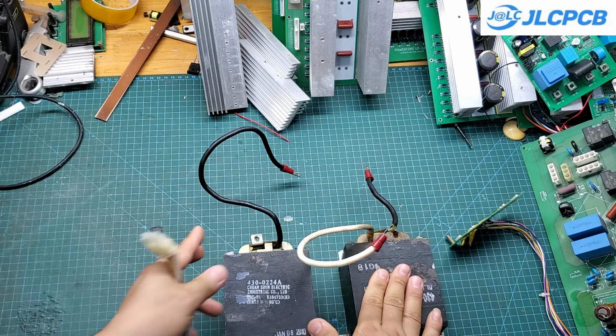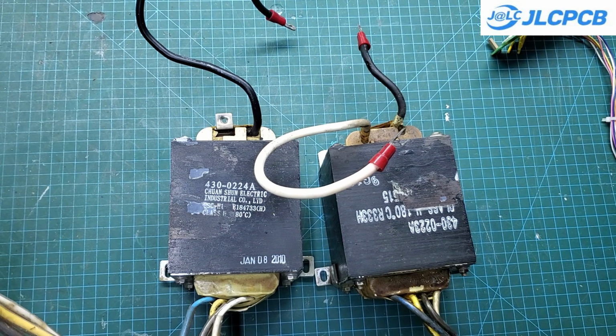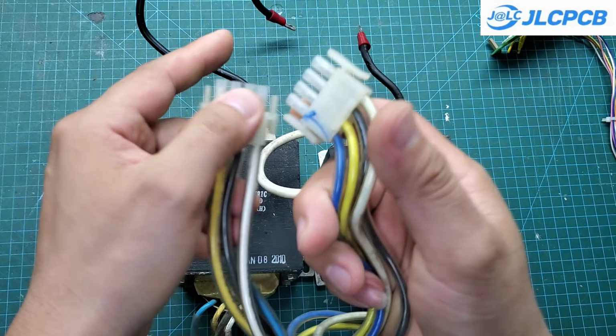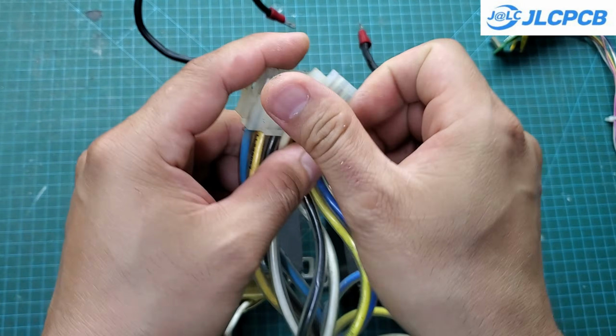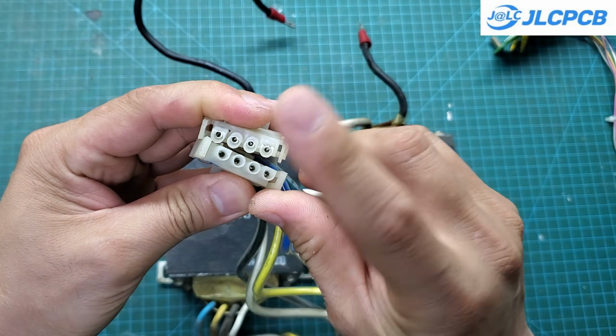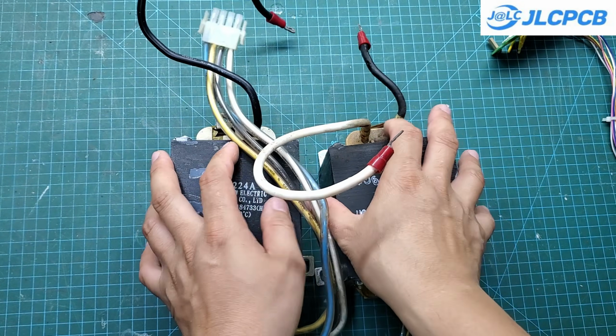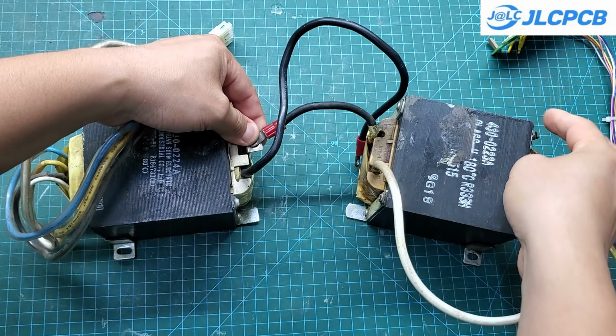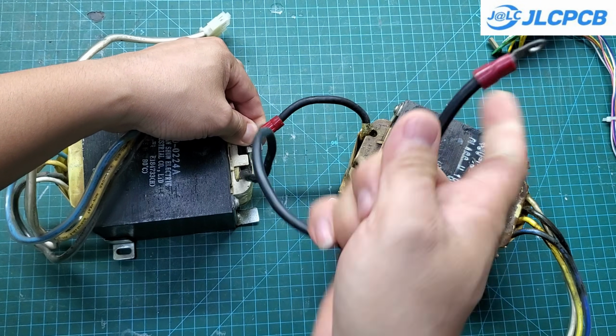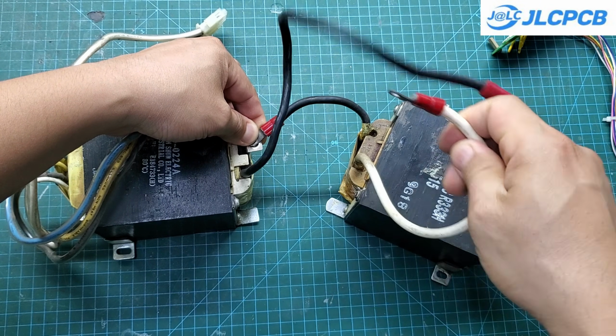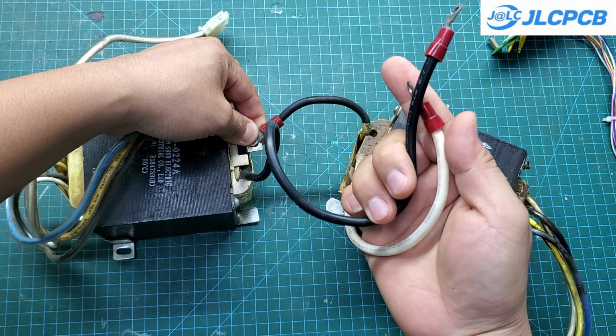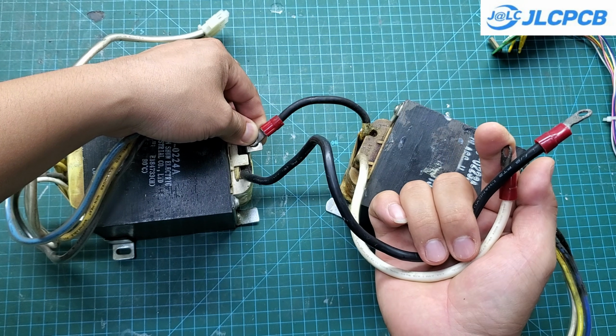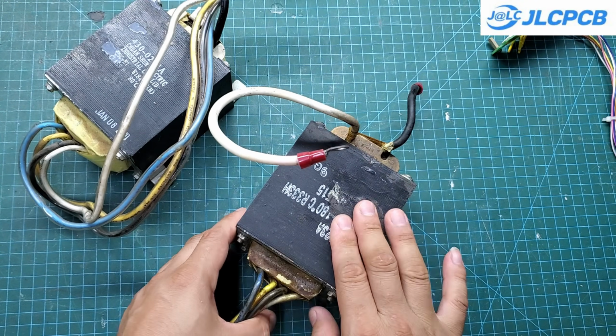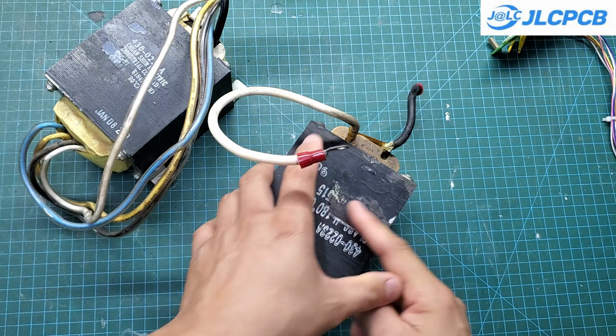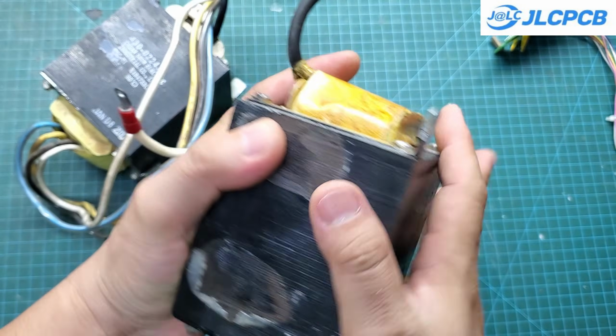Each transformer has a primary winding made from copper foil, while the secondary is split into 4 terminals with 3 different voltage levels. For our purpose, we only need the 2 outer terminals, which provide the highest voltage. The interesting part is that with these 2 transformers, we can easily use them for either a 24-volt or a 48-volt system. For a 24-volt system, both the primary and secondary windings are connected in parallel. For a 48-volt system, the primary windings are connected in series, while the 2 secondary outputs are connected in parallel.